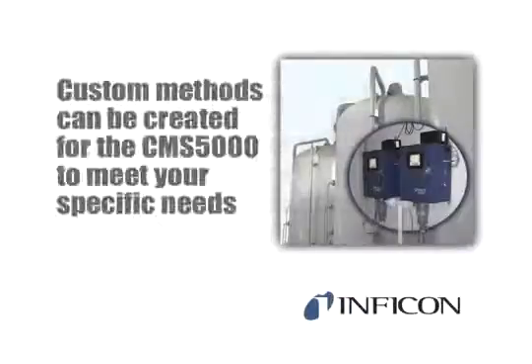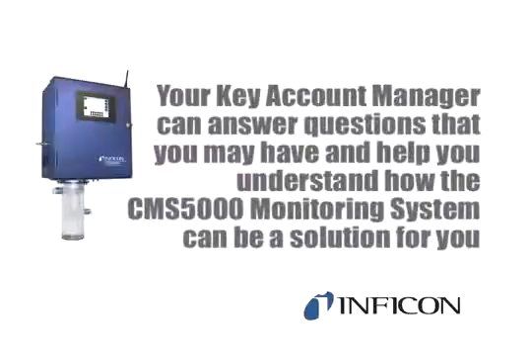Custom methods can be created for the CMS5000 to meet your specific needs. For instance, a trihalomethane or BTEX method can be developed. The CMS5000 uses GC technology, so you will need to know what analytes you would like to measure. Your key account manager can answer questions that you may have and help you understand how the CMS5000 monitoring system can be a solution for you.